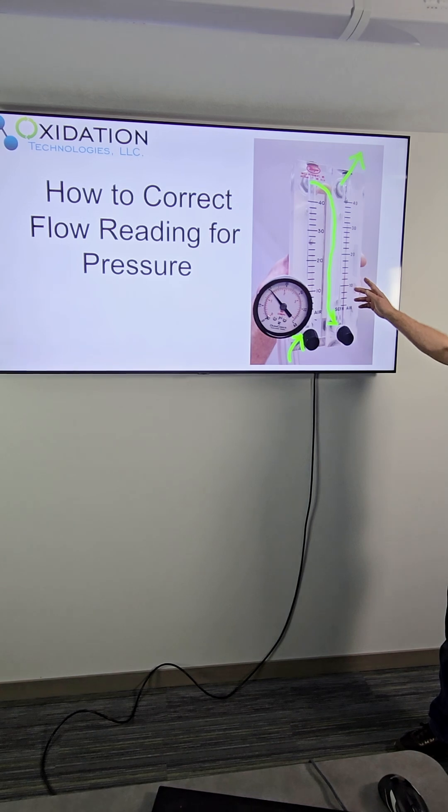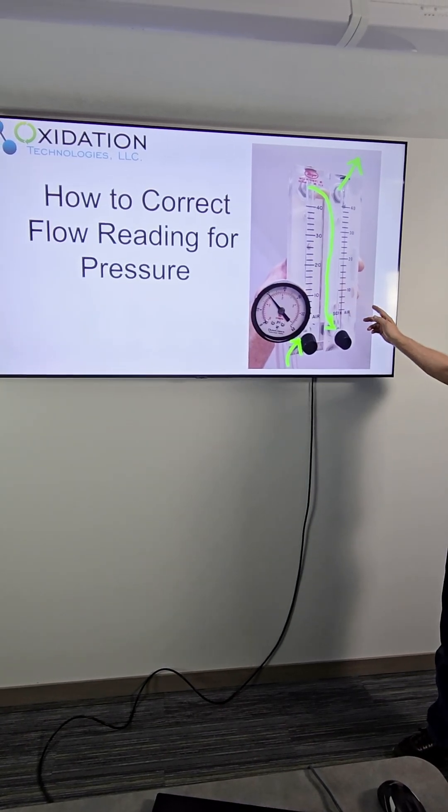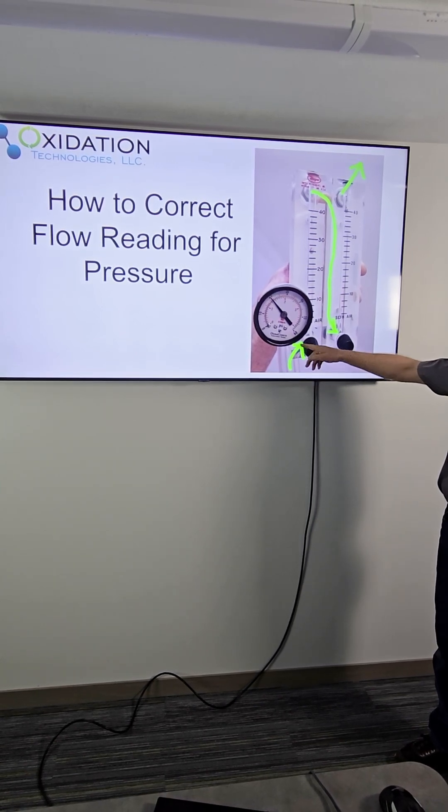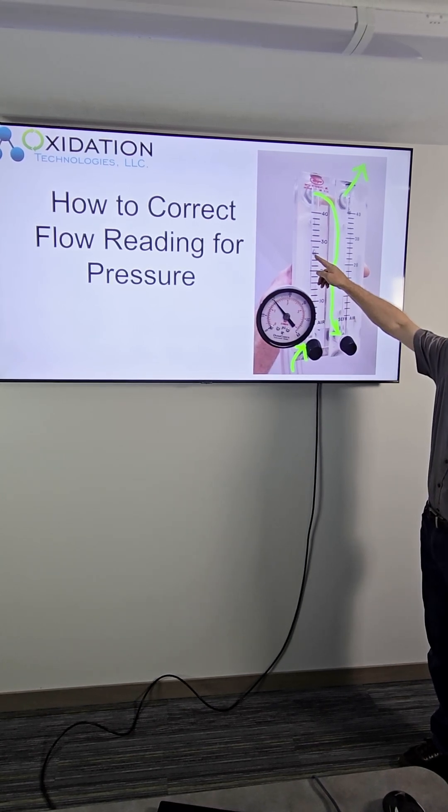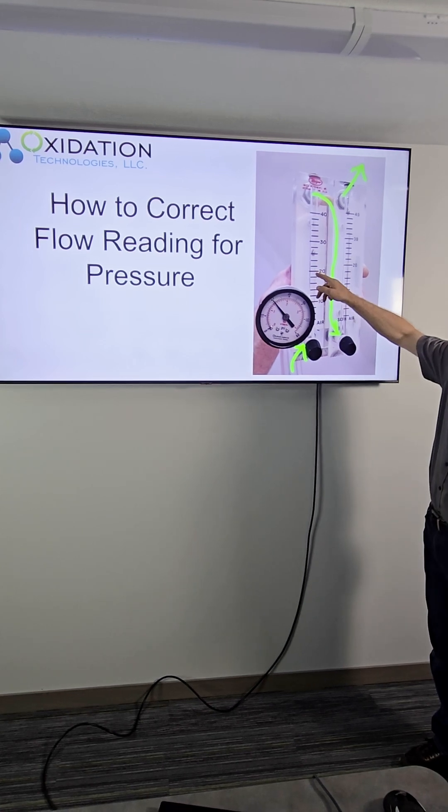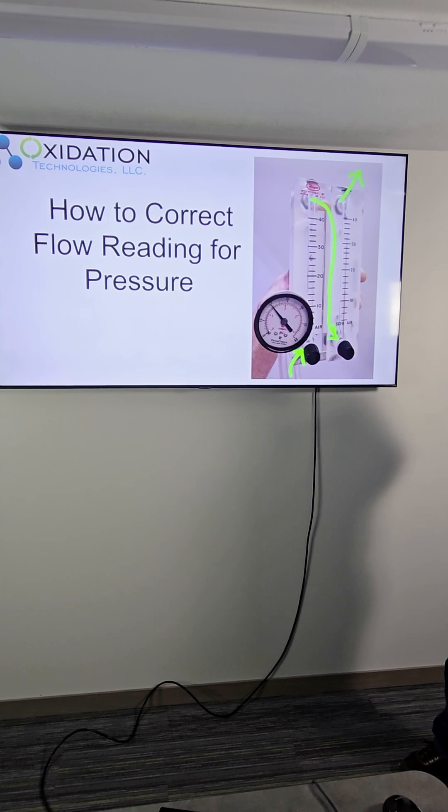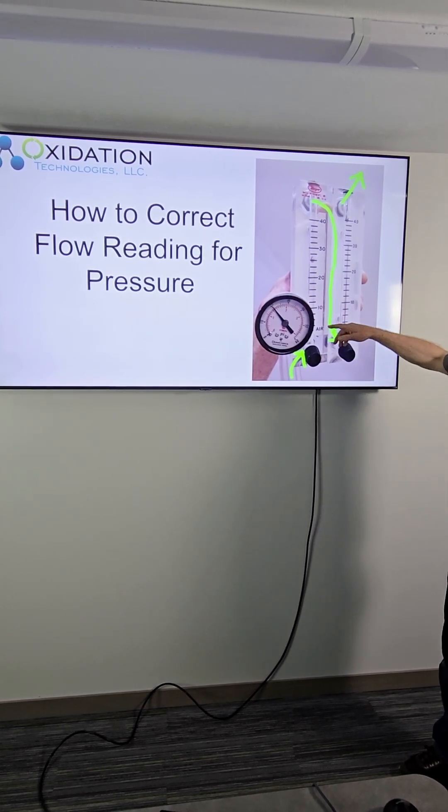So right here I've got a picture of two identical flow meters. The oxygen gas is flowing into the bottom of this one up through the tube and you can see the little ball in there that it's pushing up and it's measuring here a flow of 26 SCFH, standard cubic feet per hour of oxygen.